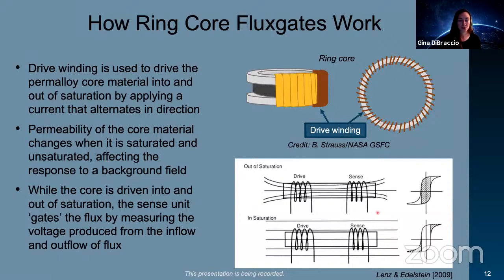Now let's talk about how the ring core fluxgate actually works. The drive winding going around the ring core is used to drive the permalloy core material into and out of saturation, by applying an alternating current. The permeability of that core material changes when it's saturated versus unsaturated, and this affects its response to the background field. While the core is driven into and out of saturation, the sense unit around the ring core gates the flux by measuring a voltage produced when the flux is going in and out of the drive winding. Looking at this figure on the right, we can talk through it in more detail.